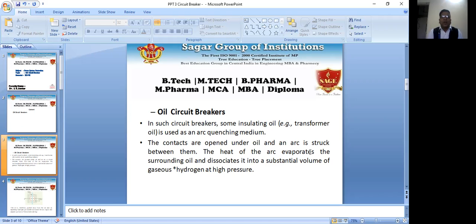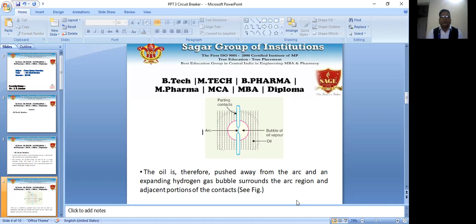Here, this is the diagram of the oil circuit breaker. This is the parting contacts, and this one is the bubbles of the vapors, and this one is the arc produced. The oil is therefore pushed away from the arc, and expanding hydrogen gas surrounds the arc region and adjacent portion of the contact. So see the diagram.